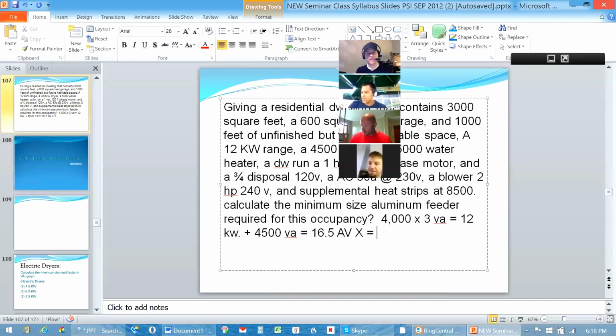So I'm going to take 16.5, and I'm going to subtract... That's not AV; it's supposed to be VA. Sorry about that. VA. I'm going to subtract 3,000 from that number because I can't touch that. So you can't touch this. No MC Hammer fans? Okay. All right. This is serious business here. That leaves us a balance of 13.5, and that's the amount that we can take a 35% derate on. So I'm going to take that balance of 13.5 and multiply it times 0.35. That's going to give me a balance there of 4.725.